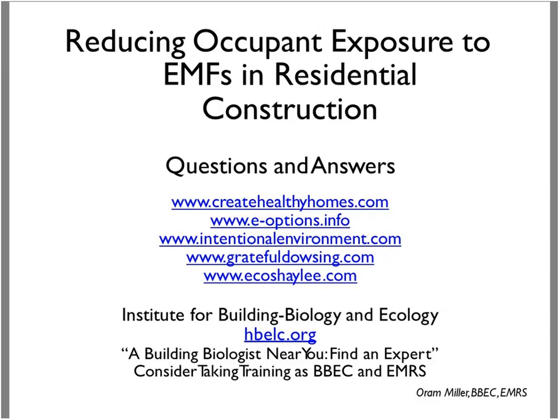Spark makes a good point: the wires are separated on utility poles because they're not insulated. They do that to save money, and because high current causes heat which burns up insulation. When the local EMF consultant for Southern California Edison came out, I met her at a client's house and asked what they do about the heat when these things are put underground. She said they are insulated, so they can be close together, but they're put in oil—there's a special paper that surrounds them that dissipates the heat, and now they use aluminum paste.